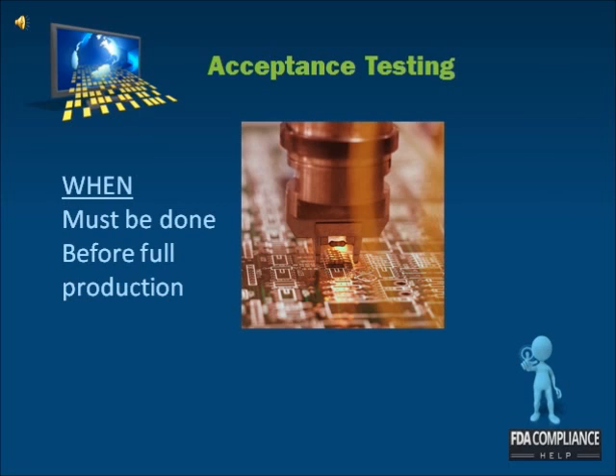The concern is that devices which are not adequately evaluated may not meet company quality claims. It is not acceptable for the facility to bypass their responsibility by simply not writing needed claims. Under Section 501 of the Food, Drug, and Cosmetic Act, a device is considered adulterated if its purity or quality falls below what the company claims or is represented to possess.